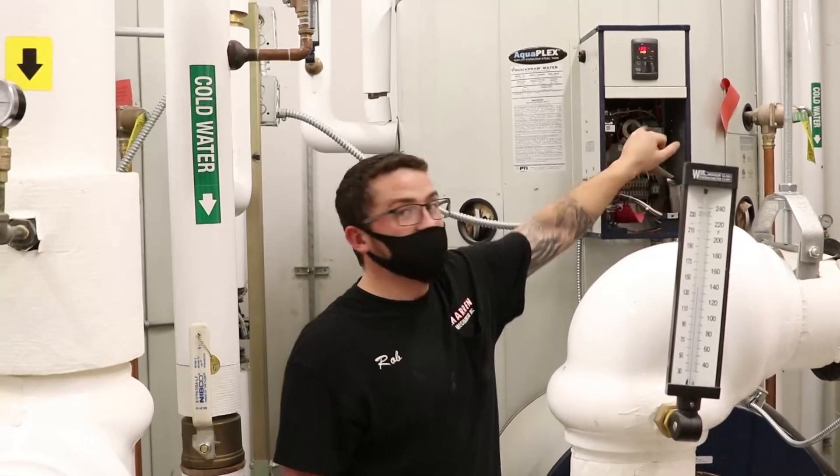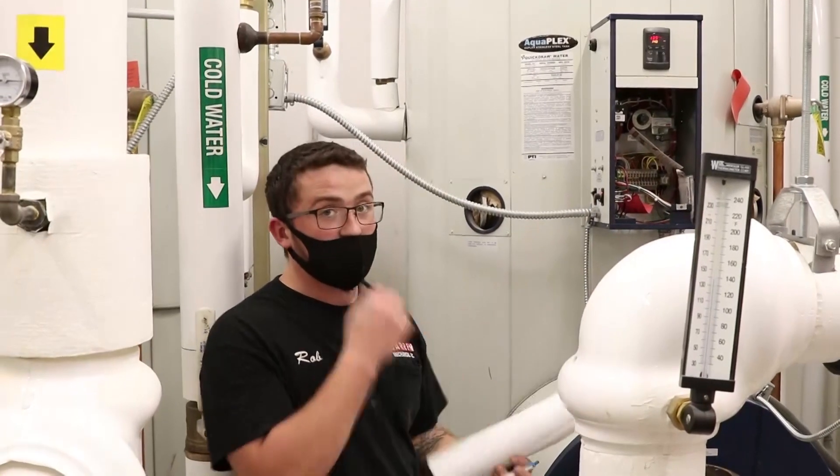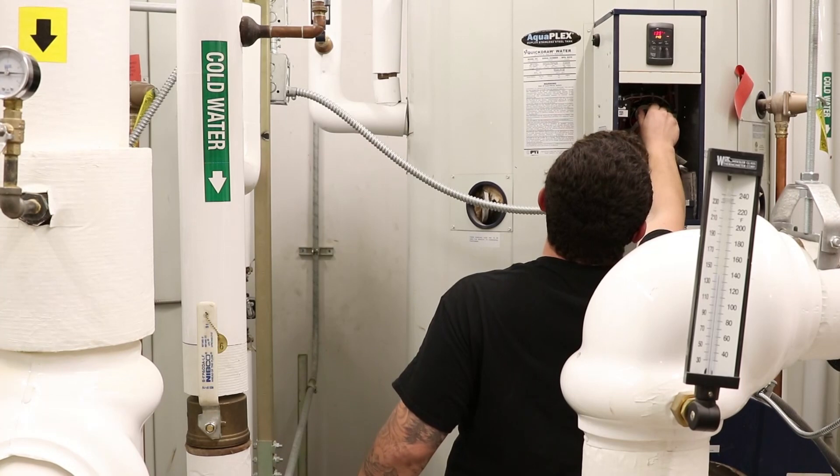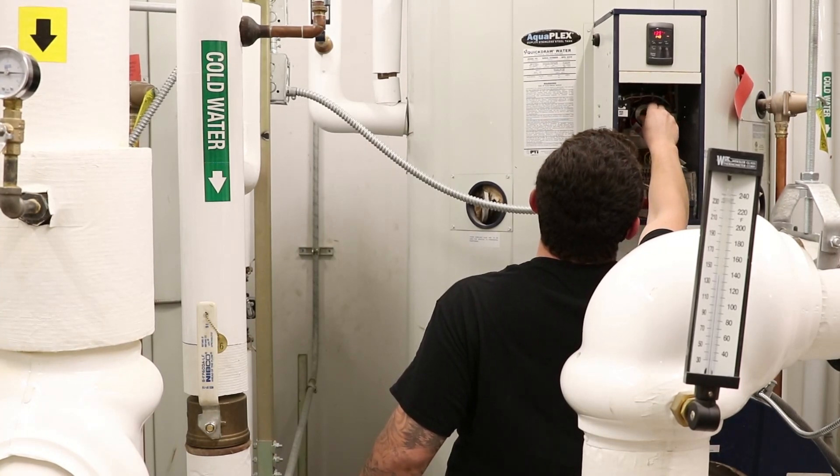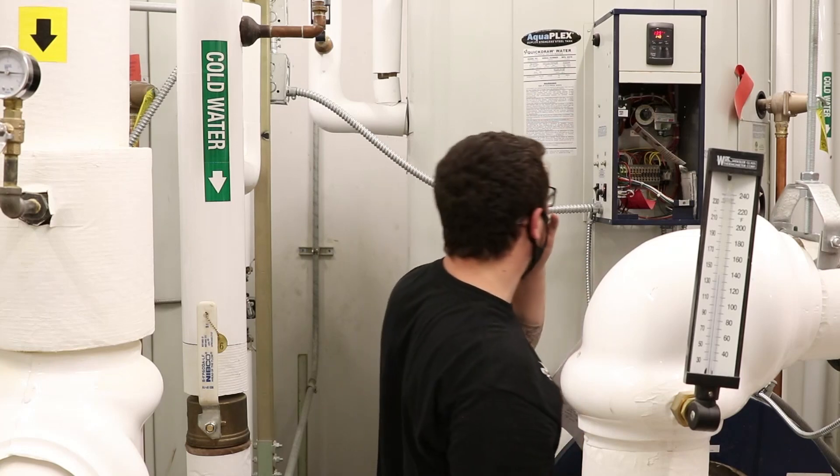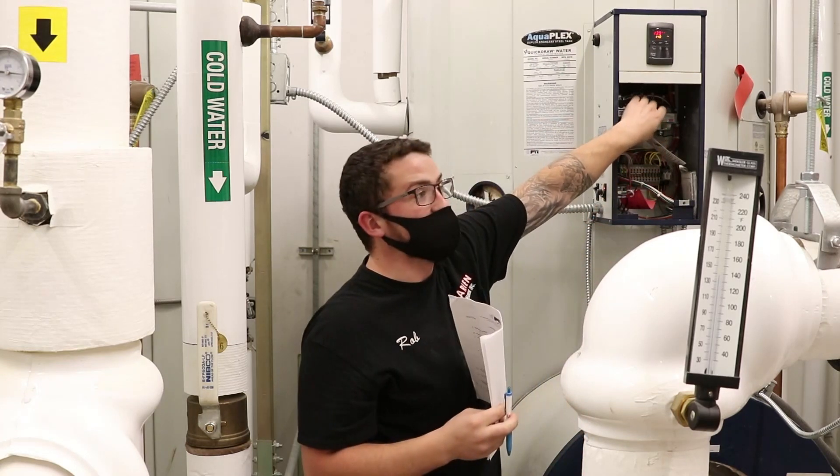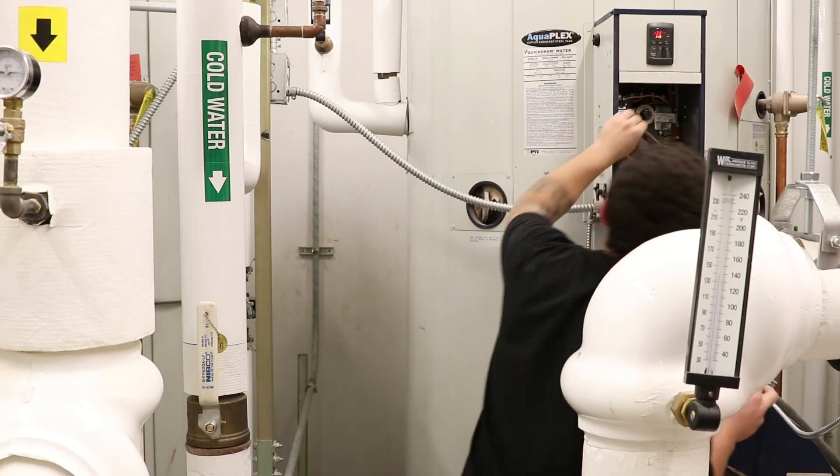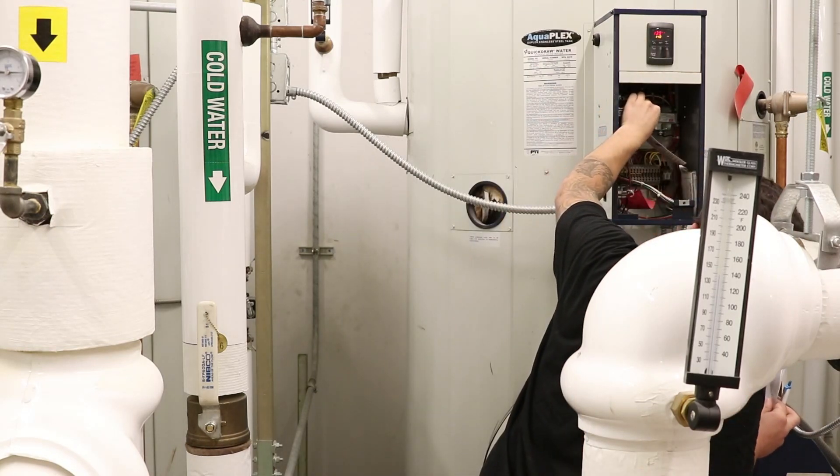This control clicks when it opens and closes, so if you touch this dial, you'll hear the control open and close. That should happen when the indicator is on the dial at the temperature that's in the tank. You'll be able to tell whether that's accurate or it's inaccurate based on when it opens and closes.